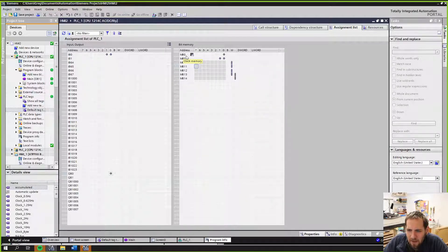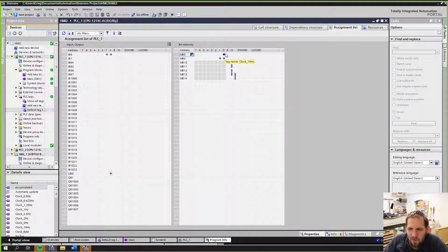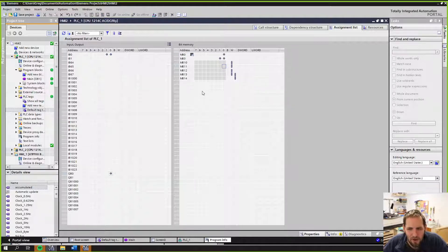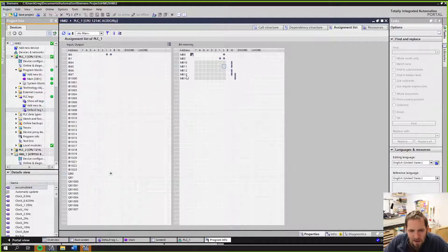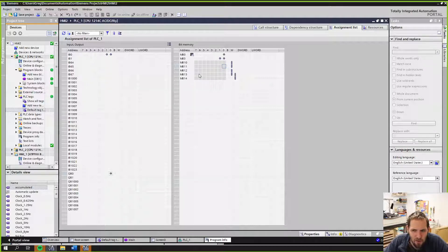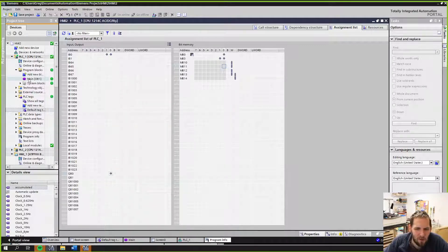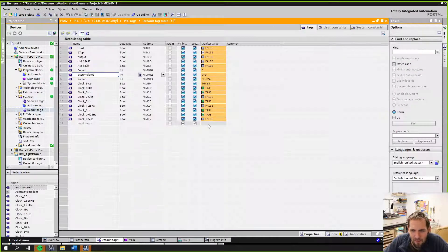Notice how it says MB0 clock memory — it even has a little clock memory icon there. It's saying we're only using the 10 Hz bit of it. This becomes really important: you have to keep track of which addresses you've used. This assignment list screen becomes critical because you might think, 'I'll just use 13, then 14,' not realizing they overlap. It would be nice if TIA Portal would automatically adjust or at least warn you when address ranges conflict.